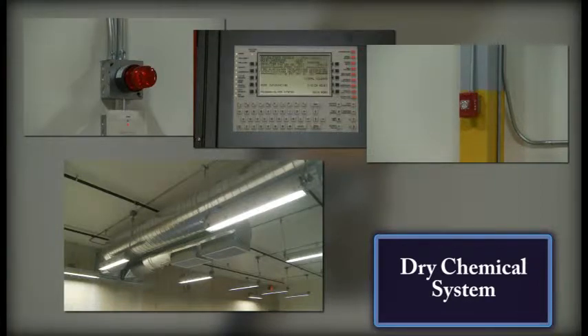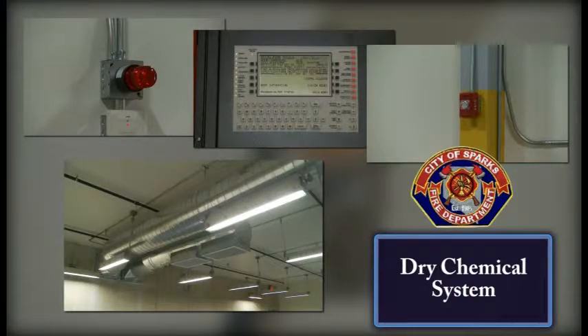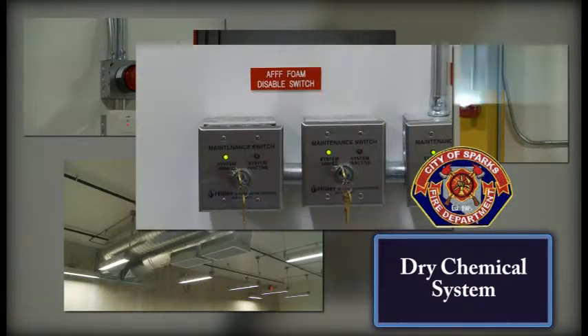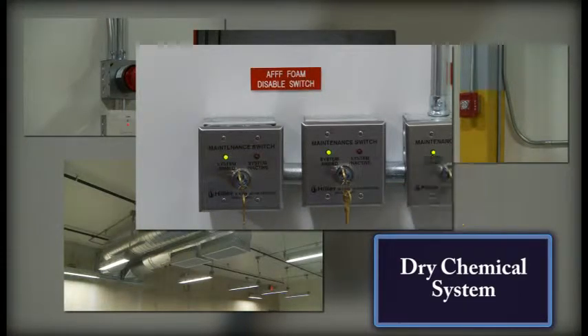If a trouble or supervisory condition is annunciated on the control panel, the Sparks Fire Department will be notified through the monitoring company. If the system is disabled using the key switch in the AFFF-AR tank room, or any addressable device is disabled, a trouble and supervisory condition will be annunciated.